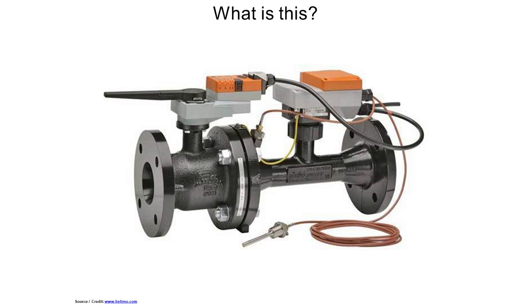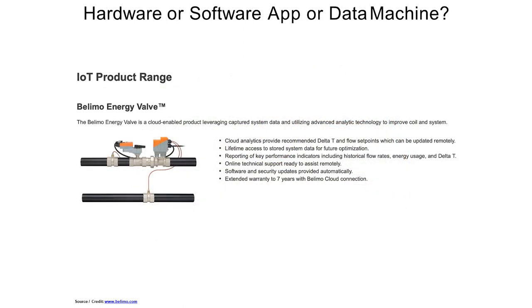I saw this at a BELIMO presentation earlier in the year—this really changed my thinking. BELIMO sell that gadget; it's a control valve, it's a commissioning valve. It measures supply and return temperature, so it can calculate BTUs in real time. It can connect to the internet, it stores data, it uploads data. It's a data acquisition machine, right?